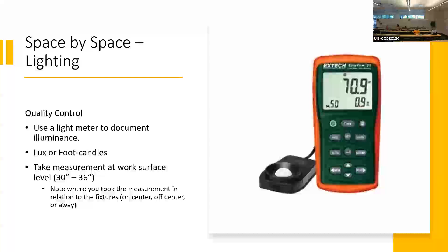So this blew me away when I saw it in a space. There's so much light for that one little desk there, and so much power being wasted. Sometimes that's obvious to me. I can tell, no problem, from my experience, but I will still put a light meter there. I will take the measurement because I have to prove and verify that that is what's happening. It's always easier to do with scientific data.